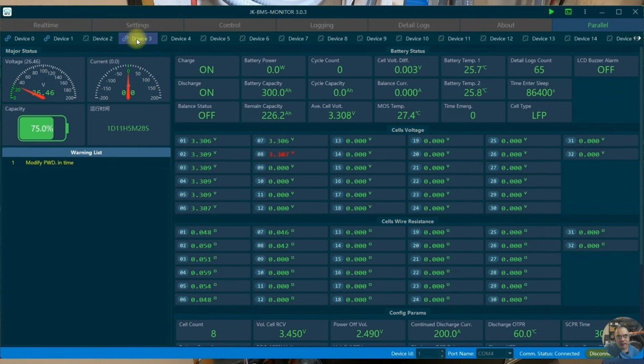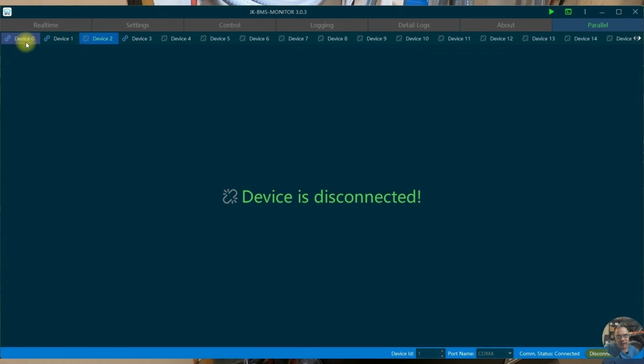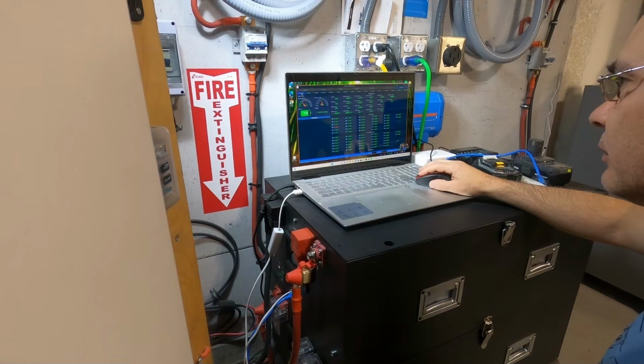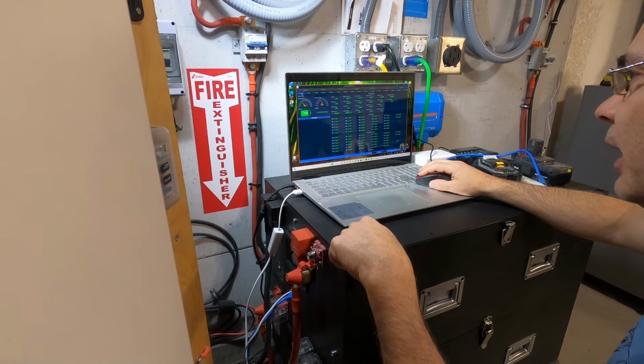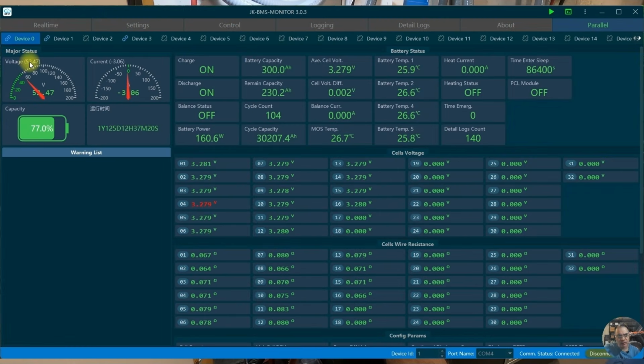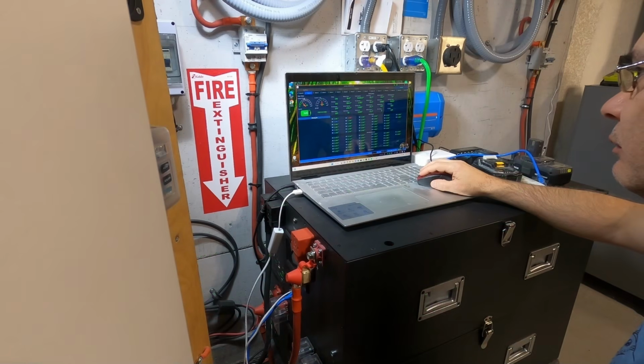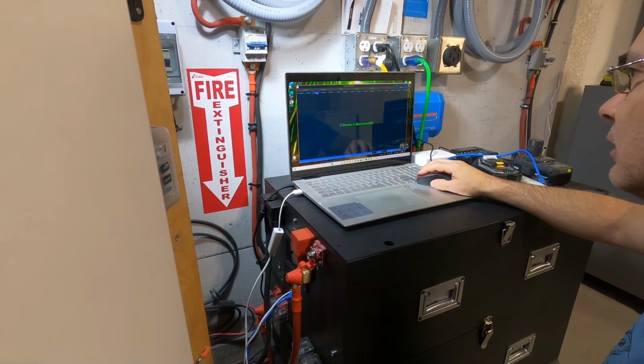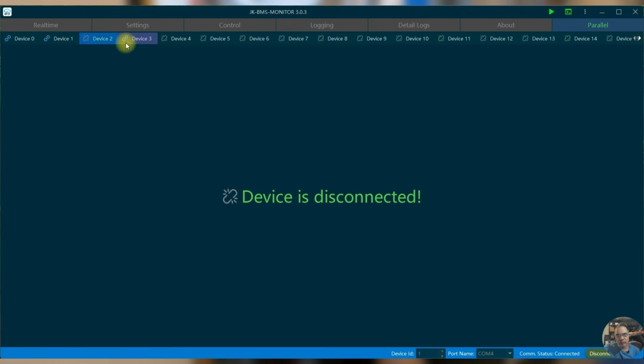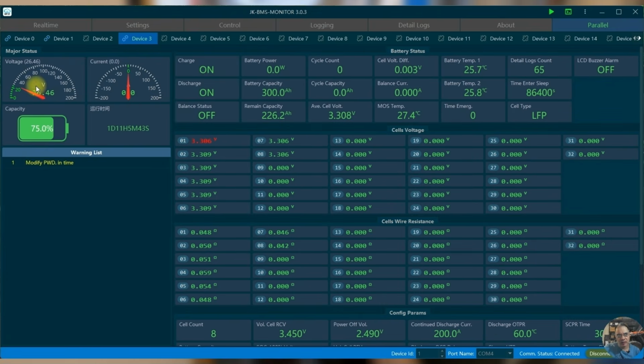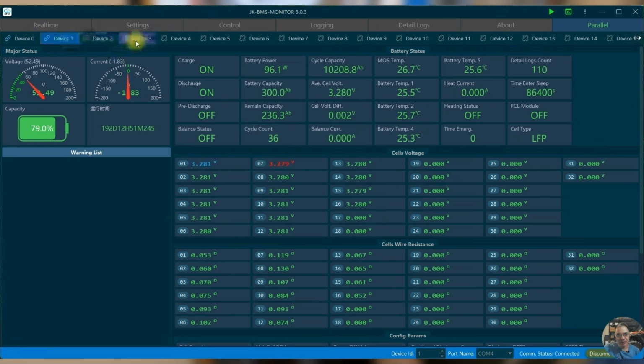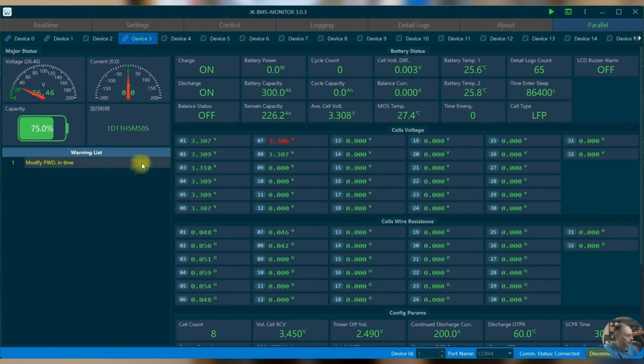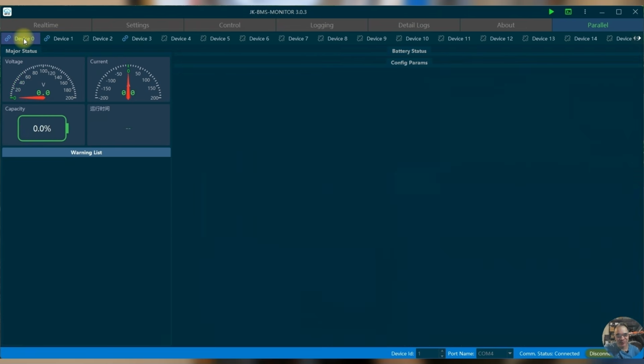And there it is, device 3. So we have nothing on device 2, so we have 0, which is the first 48 volt battery. We can see 52 volts. The second one down here, 52 volts. Nothing on device 2. And the device 3, it's our 24 volt battery. You can see 26 volts here. So we're monitoring JK inverter BMS and a B-Series BMS all on the same bus. How cool is that? JK, man, I swear, that just works.